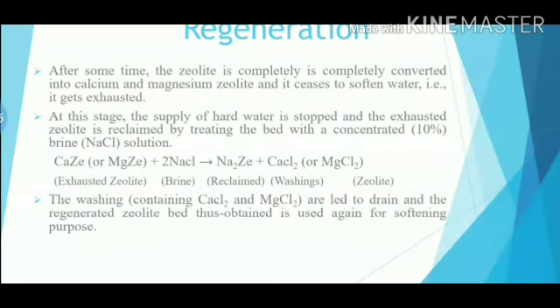Now, regeneration. After some time, the zeolite is completely converted into calcium and magnesium zeolite and it ceases to soften water, i.e., it gets exhausted. At this stage, the supply of hard water is stopped and the exhausted zeolite is reclaimed by treating the bed with a concentrated 10% NaCl solution. Now, the washings containing CaCl₂ and MgCl₂ are led to drain and the regenerated zeolite bed thus obtained is used again for softening purpose.